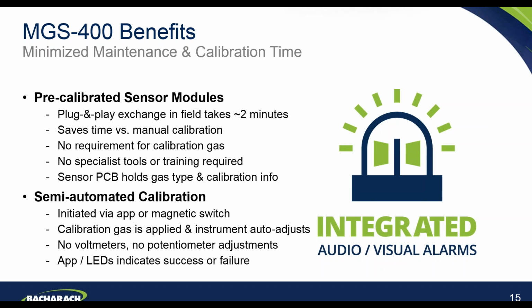The smart aspect of the sensor modules really is the PCB that is mounted onto the sensor module itself. The PCB holds all of the gas type and calibration information for that sensor. In terms of the calibration process itself, you can initiate that via the app, which I'll show you in some greater detail shortly, or via the magnetic switch. So each MGS-400 series detector will come with a small magnet, and that is required to switch the magnetic switch. There's actually 2 magnetic switches in the bottom of the detectors themselves, and you can use one of those magnetic switches to put the unit into calibration mode.